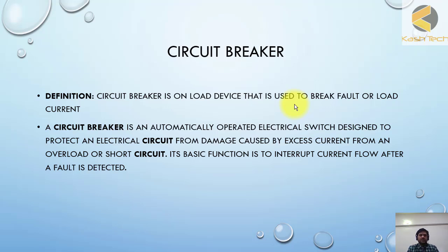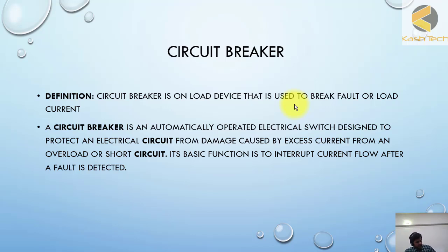A breaker is basically a device designed to break the fault current. If there is a fault, it will break the fault current. You can also use this breaker to interrupt the power — for example, to switch off. In our houses we see a simple switch to turn on and off because at low levels you don't need a specialized interrupting unit, but at high voltages and high currents a special mechanism and special arrangement is required. A special interrupter unit is used to break the load current; otherwise the current will not be broken and the fault or load current will cause a continuous spark that can damage the breaker.